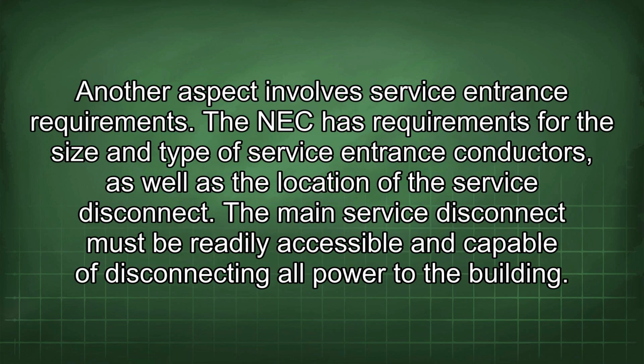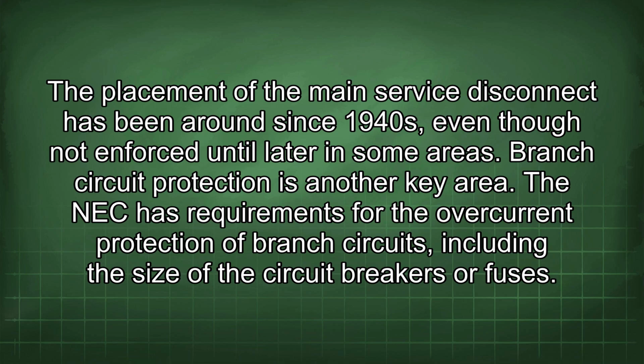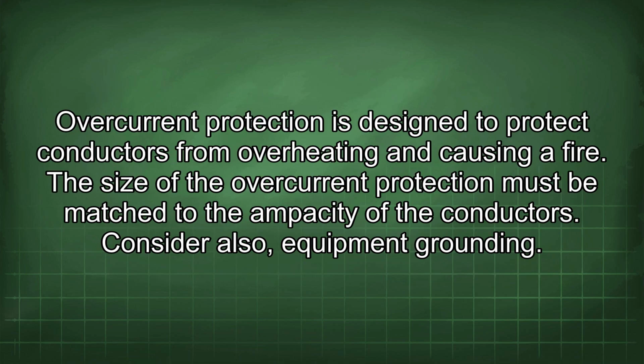Another aspect involves service entrance requirements. The NEC has requirements for the size and type of service entrance conductors, as well as the location of the service disconnect. The main service disconnect must be readily accessible and capable of disconnecting all power to the building. The placement of the main service disconnect has been around since the 1940s, even though not enforced until later in some areas. Branch circuit protection is another key area. The NEC has requirements for the overcurrent protection of branch circuits, including the size of the circuit breakers or fuses. Overcurrent protection is designed to protect conductors from overheating and causing a fire. The size of the overcurrent protection must be matched to the ampacity of the conductors.